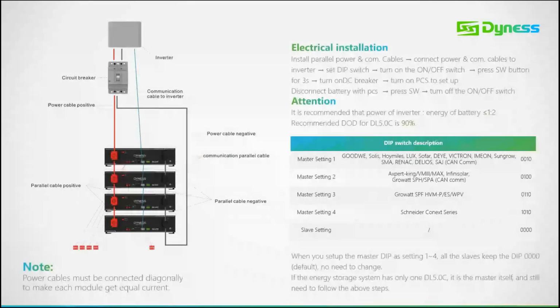Okay, our DL5.0C, BX51100 and A48100 pretty much have the same layouts or connections when it comes to electrical installation. So starting with the inverter, it's from inverter to circuit breaker, from circuit breaker to positive of your master battery, from circuit breaker to negative of your last slave battery.